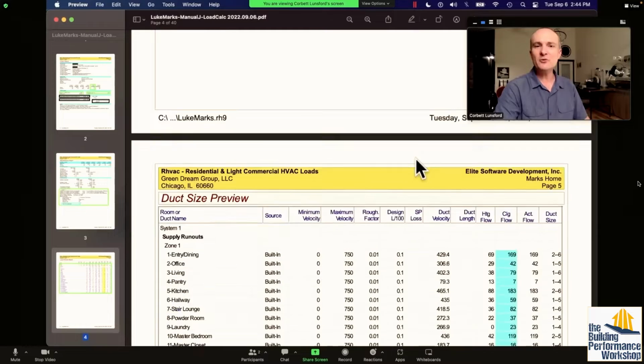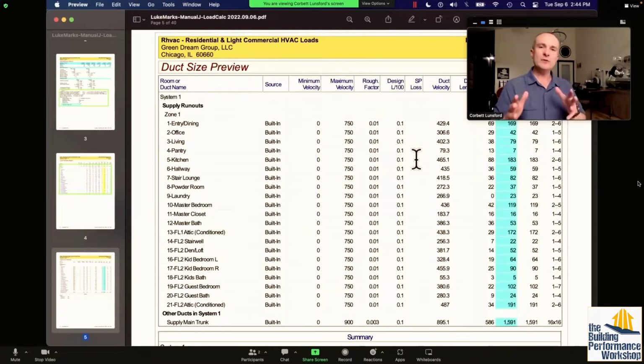So what I'd like to do first is Manual J calculations. I hand off Manual J reports to people all over the country for their projects, and I try not to have them upset their HVAC installer with it. Good luck. One of the things in there, if you print out the full report, which I try to give people as a 20 to 40 page report if possible, for the HVAC guys doing this, please just show your work, that's all we're asking. When I give them a full report, there's a page that says here are the duct sizes you should use, and here are the CFM required for each room. Can you dig into that a little bit?